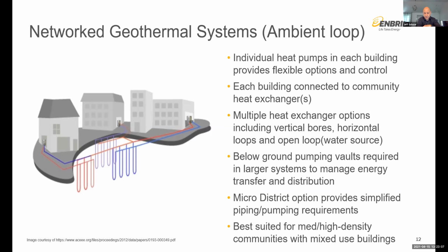There are multiple heat exchanger options that can be incorporated here. You could have verticals, as are shown in the picture here, and have a number of them throughout the community. You could also tie in a horizontal system underneath a park space or a green space, and interconnect all of those heat exchangers into the central ambient loop that basically distributes that thermal energy through the community, and the heat pumps harness that energy as required. These are great for medium to high density communities, especially when there's a mixed use of buildings in the community. So if you have a large number of residential family homes and also some commercial and retail space, or potentially a community center that has a year-long heating load or cooling load for an ice rink or a pool system, these are great for energy sharing.